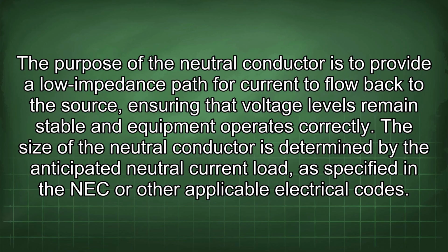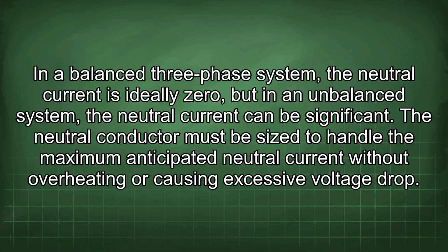The size of the neutral conductor is determined by the anticipated neutral current load, as specified in the NEC or other applicable electrical codes. In a balanced three-phase system, the neutral current is ideally zero, but in an unbalanced system, the neutral current can be significant. The neutral conductor must be sized to handle the maximum anticipated neutral current without overheating or causing excessive voltage drop.